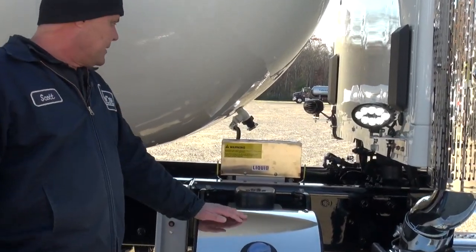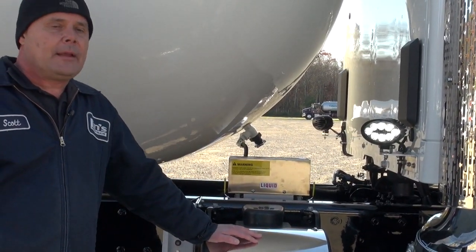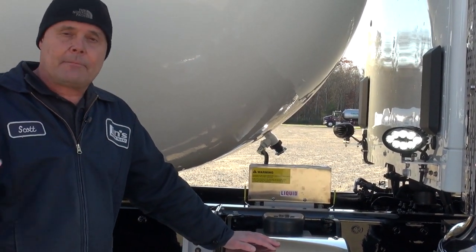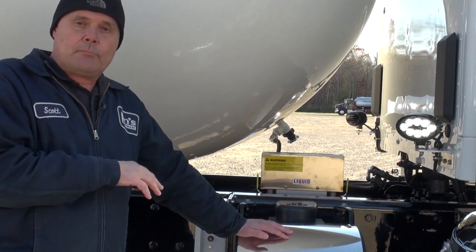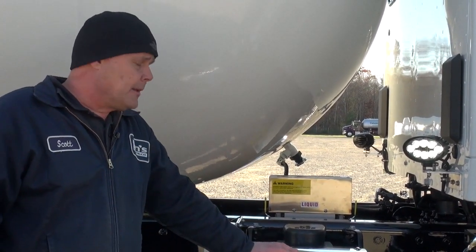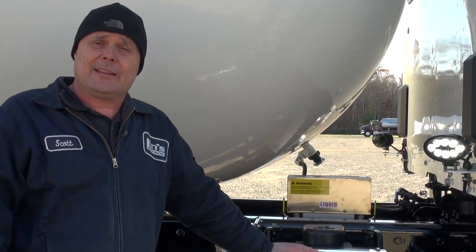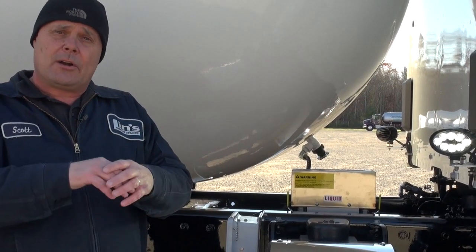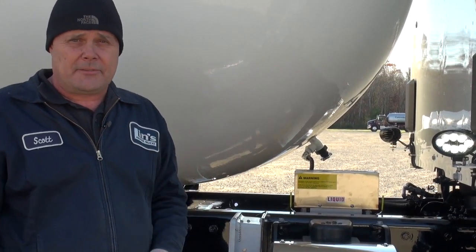What that's doing is basically heating propane and putting it back up into the head of the tank. So the whole time you're delivering, you're taking pressure out of the tank. Your tank is boiling to replace it, reach its equilibrium again, and those bubbles are going into the pump and making it less efficient. Anytime that pump isn't fully filled with liquid, you've got all those vapor bubbles in there, it becomes less efficient.